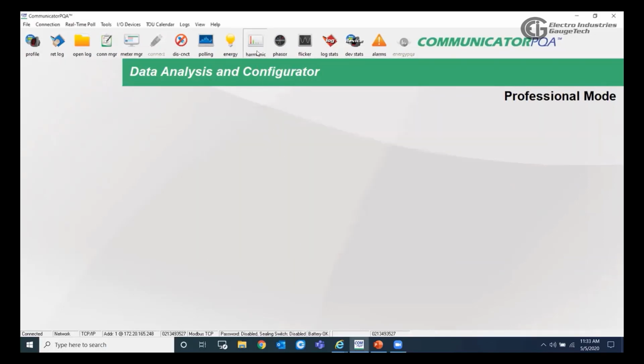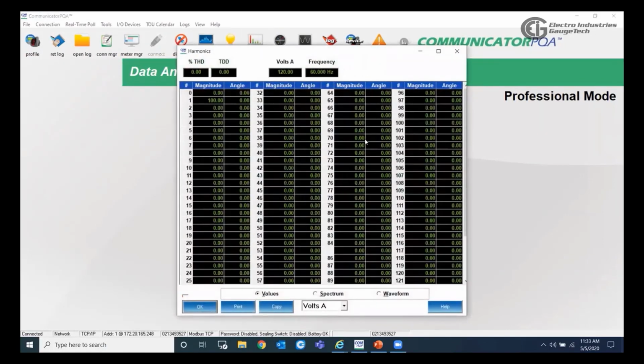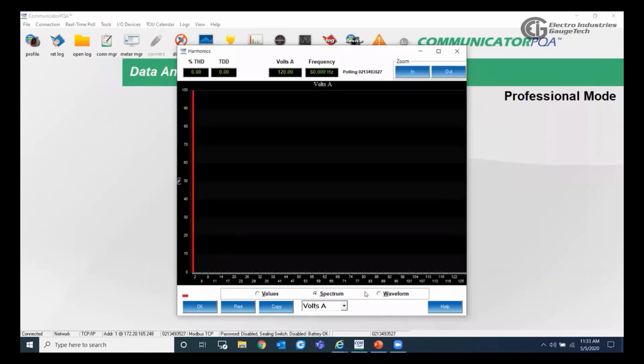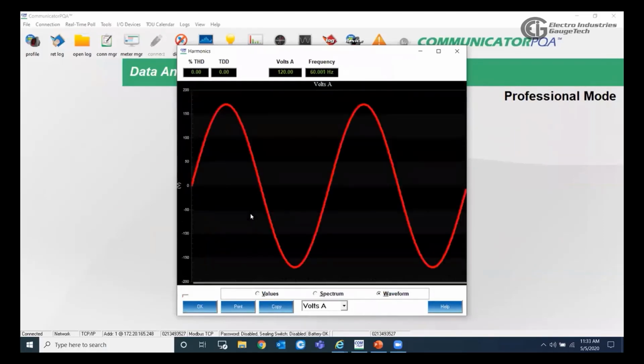The next one would be the harmonics. As you can see, we can look at all these harmonics readings up to the 127th order. And also we can see the total harmonic distortion. We can also have the option to do a spectrum or waveform if there is a harmonic there.